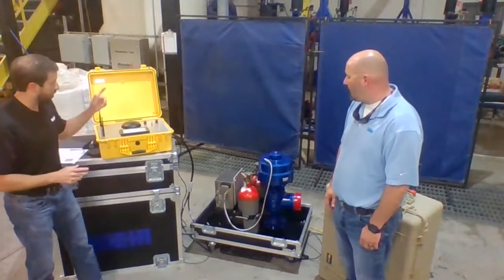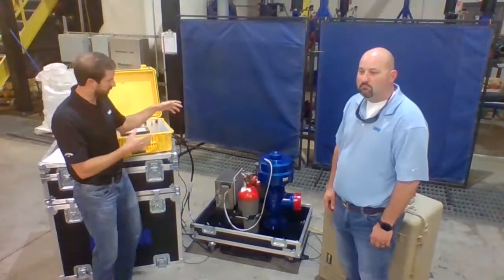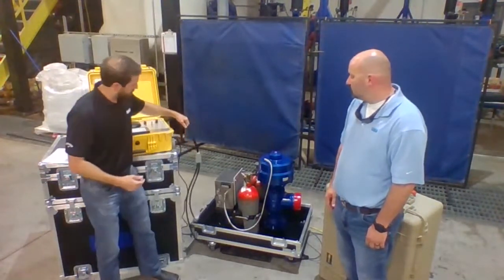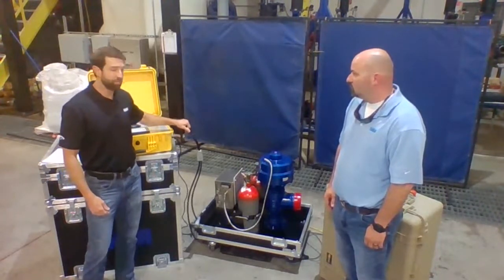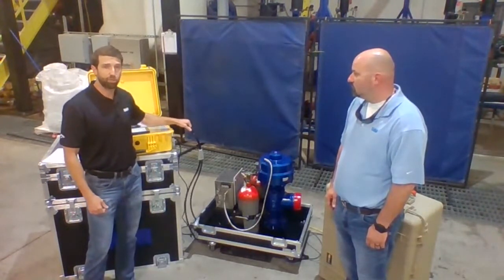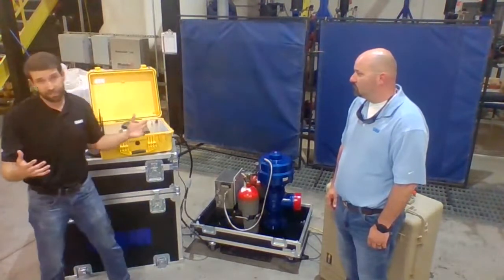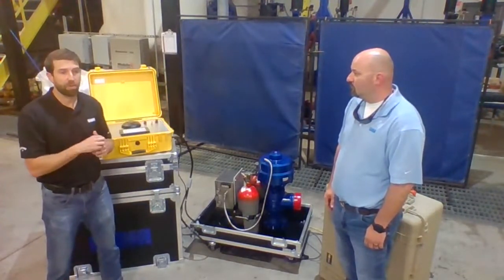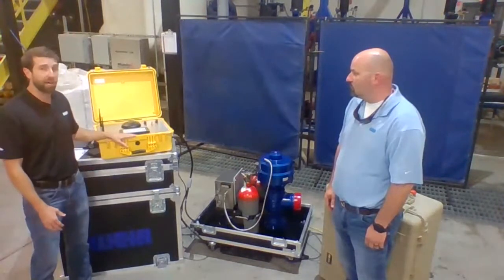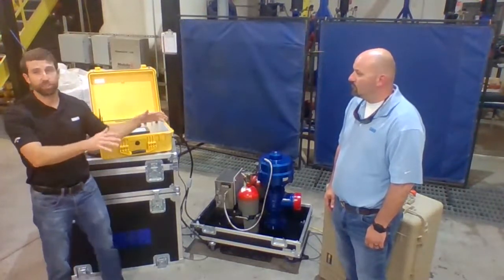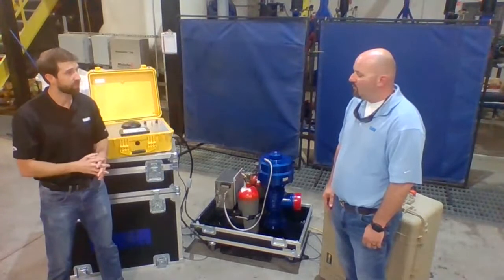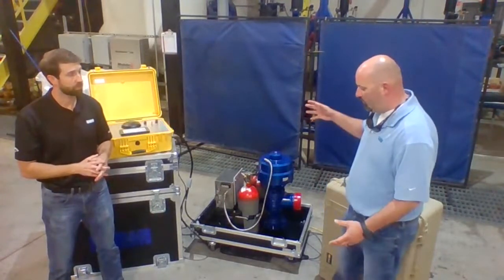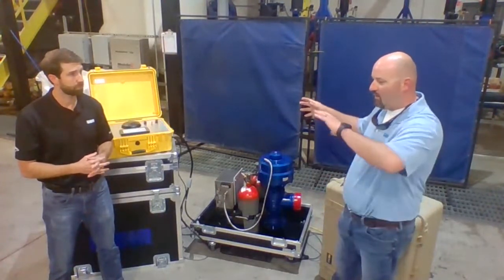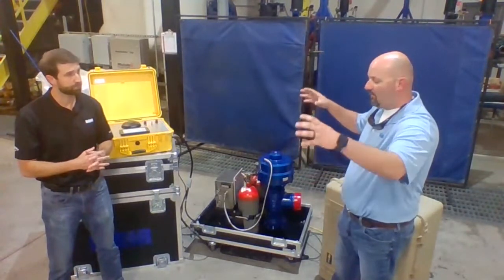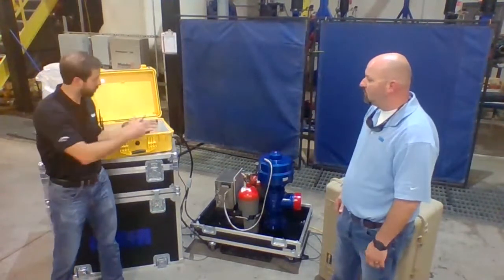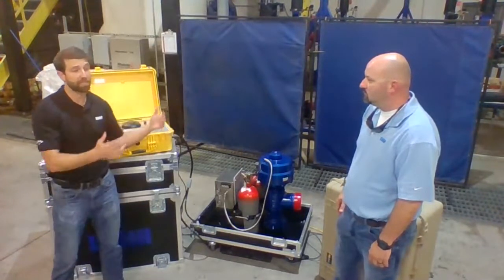One more thing to touch on here: a standard feature of this system is a Y-cable coming out of our control box. This means that on site, with a single control box, we have the ability to control two different valves at two different set pressures—for example, one by the manifold trailer and one on the other side at the plug valves, each at separate pressures. You can run two cables out to two different valve boxes.